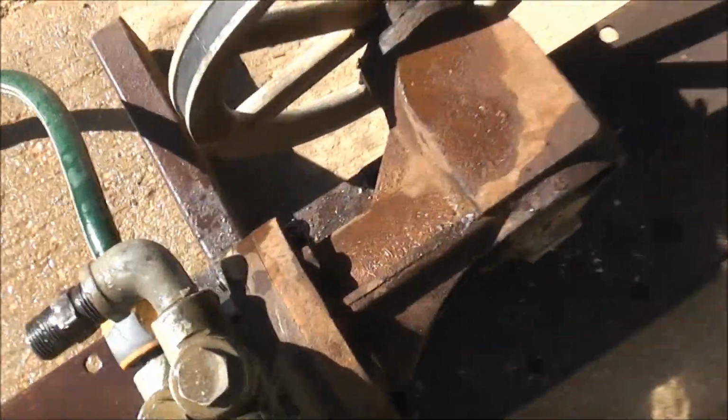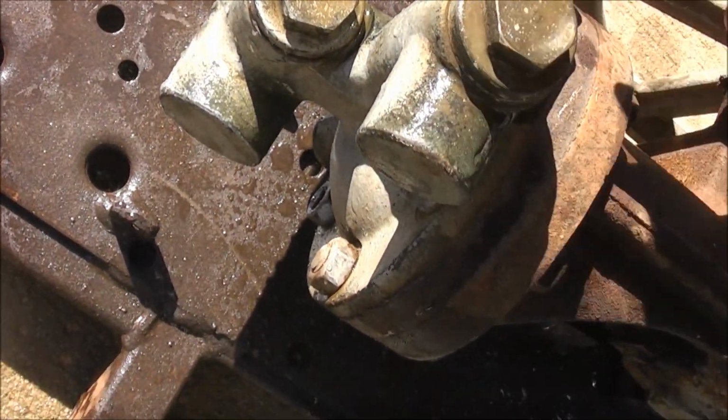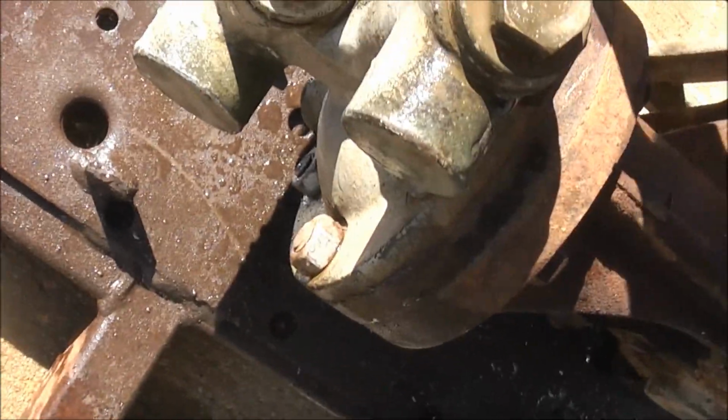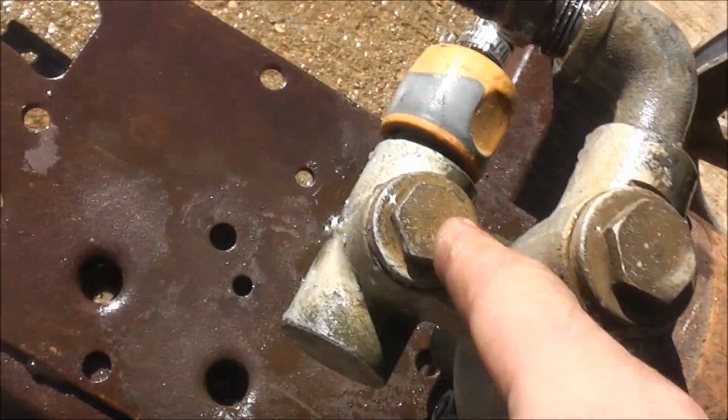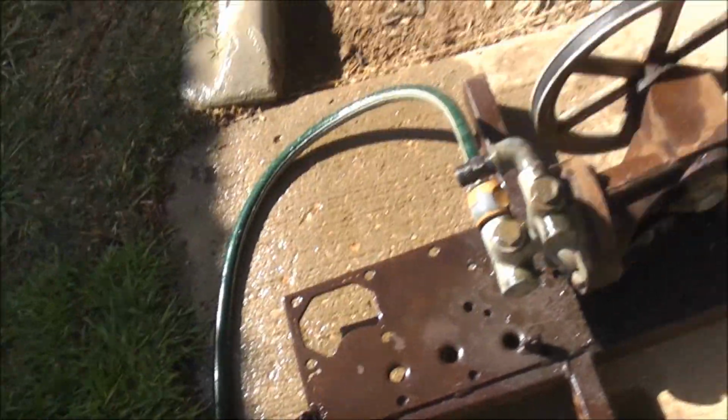That means it pumps in there, it's in good condition without any leaks. Now in here there should be some check valves. So that's definitely the discharge, and I've got the input there. If I pull these off, I can have a good look inside at how that all works. I wonder if there's any adjustment in there. Let's have a look.